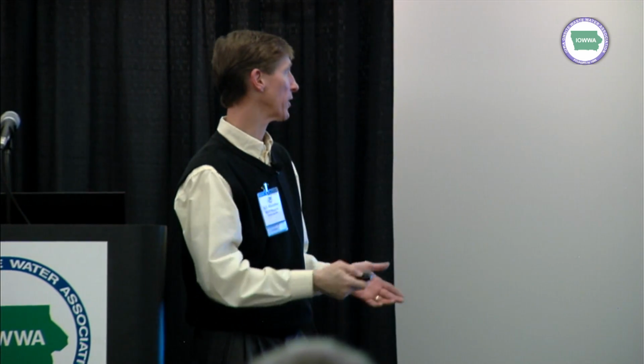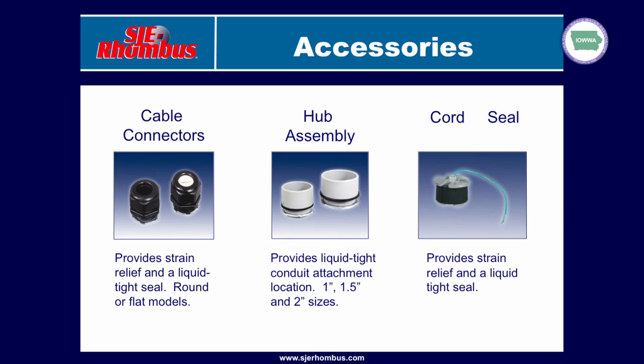So a couple of examples: we've got what I would call liquid tight fittings that would work for individual cables. These are available for flat cables or round cables. We can also do conduit hubs so that you can bring in multiple cables through one penetration. If you use a conduit hub like that, I recommend that we seal that off if it's going back to a sewage environment. If we've got conduit running from our control panel back to a pump tank or the septic tank, you've got sewer gas in there, and that conduit not only brings your wires over to the panel, it's also going to bring sewer gas.